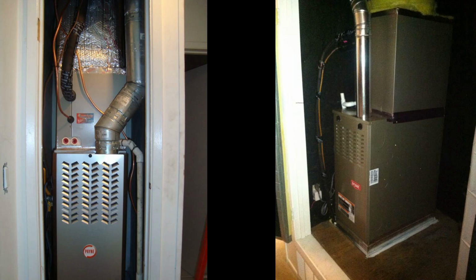But the flue they're talking about is that galvanized flue pipe that you see just on top of the gas furnace. That is a double wall. It is drilled in with 1/4-inch self tappers or 5/16, depending on the technician. I like to silver tape the connections as it goes, just for an added safety measure. But this is a complete setup.